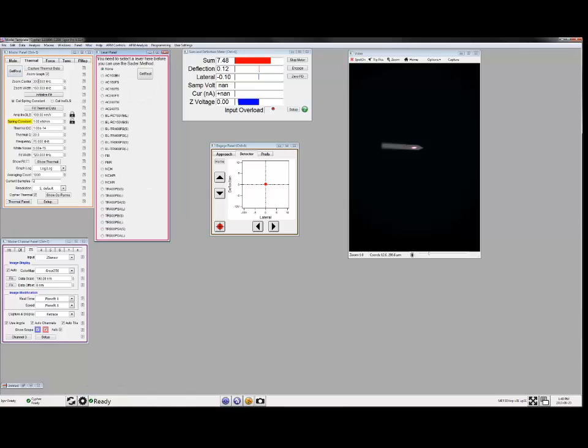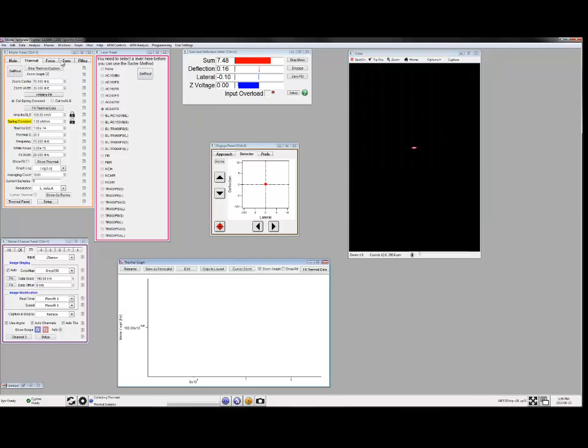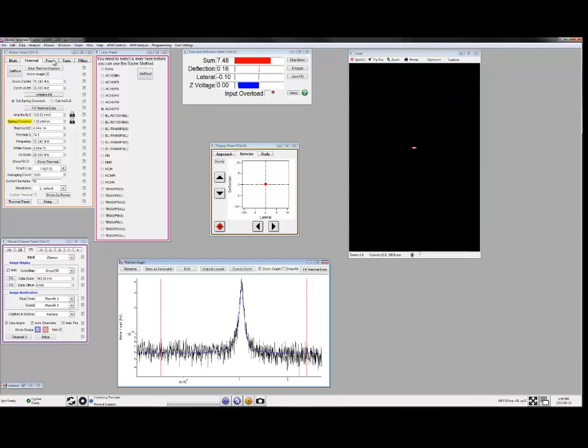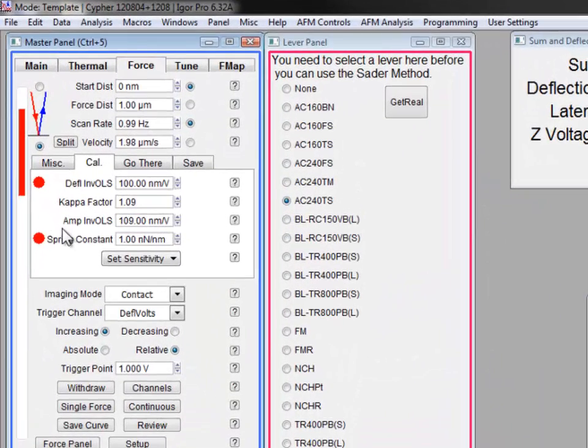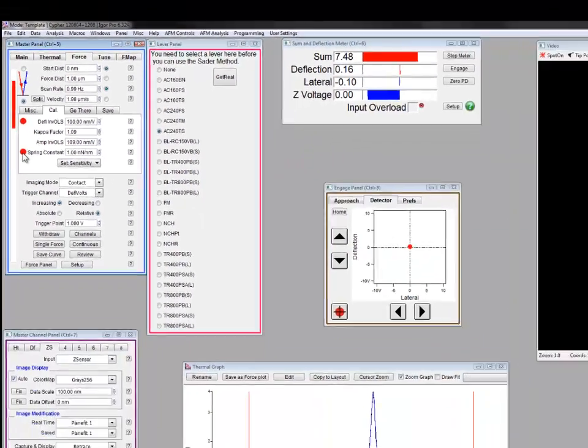When I press that button, the cantilever panel comes up and I can see a selection of cantilevers that are available to use with the method. Since I'm using an AC240TS cantilever, I'll go ahead and select that from the list. I'll now start the procedure by pressing the GetReal button. As the procedure starts, I want to show you the Calibration tab of the force panel, and here we'll see that none of my calibration factors have been calibrated. That's indicated by the red dots on the left.